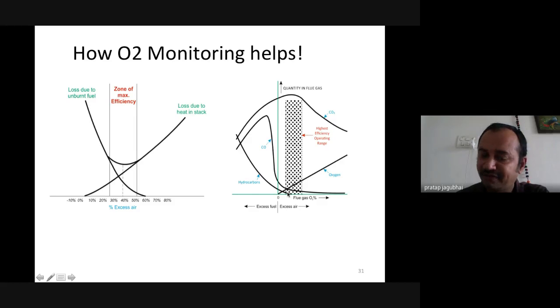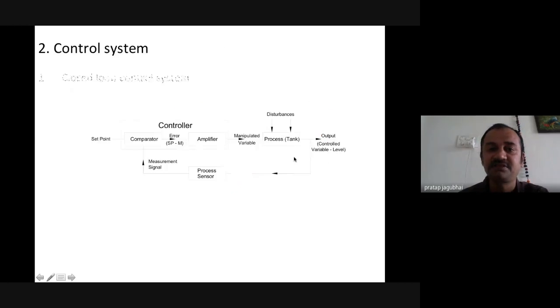efficient zone. If we don't give sufficient oxygen, then there is a sudden rise in the unburnt CO. Again, it's unburnt loss. And if we give higher oxygen, then there is a sudden rise in oxygen, and so the dry flue gas loss, the stack loss, will be higher. So we should be very near to this efficient band. That will ensure our combustion control optimization.